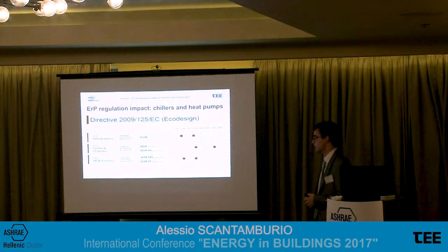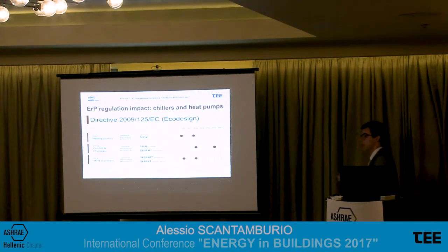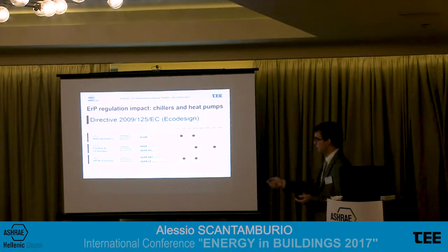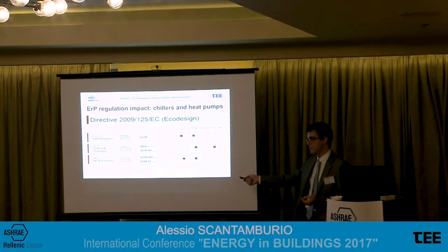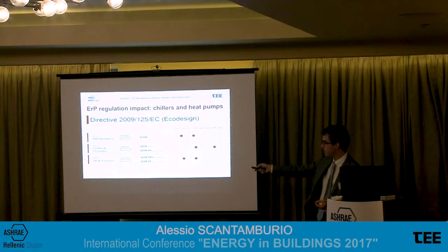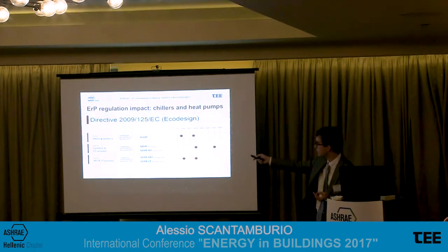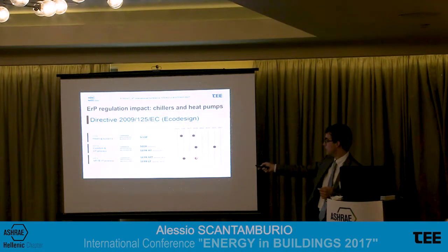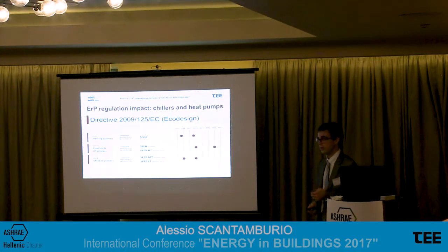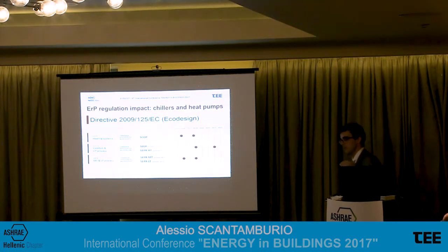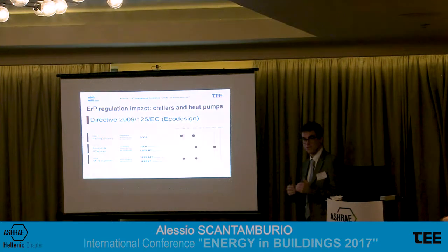Same time schedule. So again, next January both the comfort cooling parameters and the process cooling high temperature parameters will enter into force. Then if we have a process that requires fluid at a lower temperature, -8 or -25, we must be compliant with these two parameters covered by this regulation, which is different from this one. We have -8 and -25, and it will enter into force in the second tier, because the first tier has been active since two years ago, more or less, next January again. So next January we will have both comfort cooling and process cooling entering into force and setting high efficiency levels in terms of seasonal efficiency, part load efficiency.